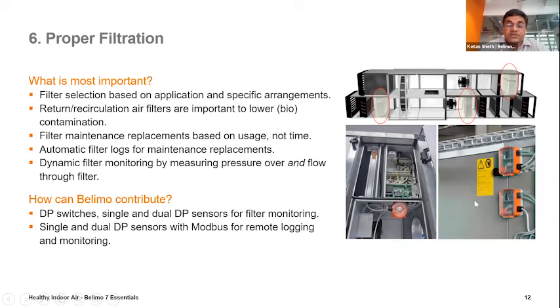Another way of measuring is with single and dual, one port and two port pressure sensors for filter monitoring, where we have a larger number of filter banks. These filter banks or sensors are also available with communication, wherever we have many filters and other things to be monitored, for raising alarms. And by using communication technology, we can also save some IOs from the BMS point of view.